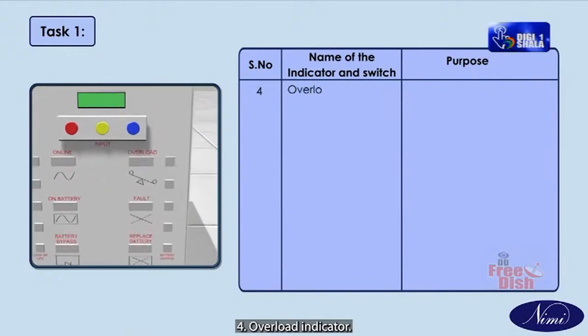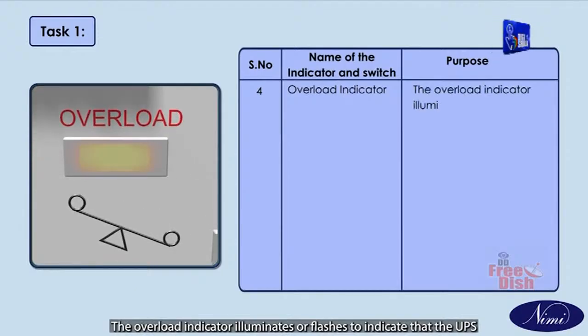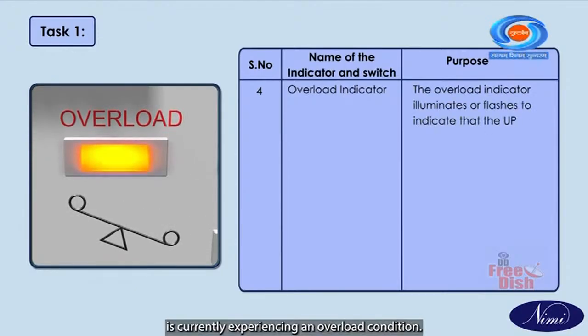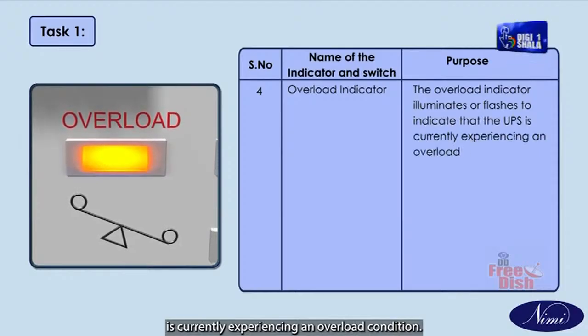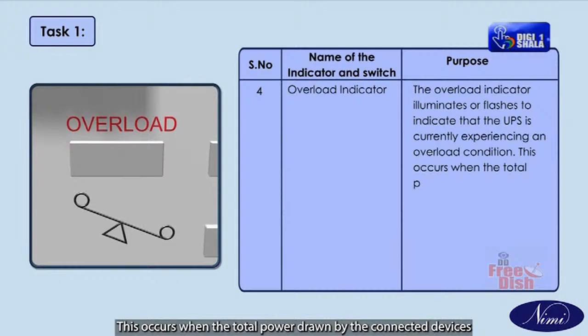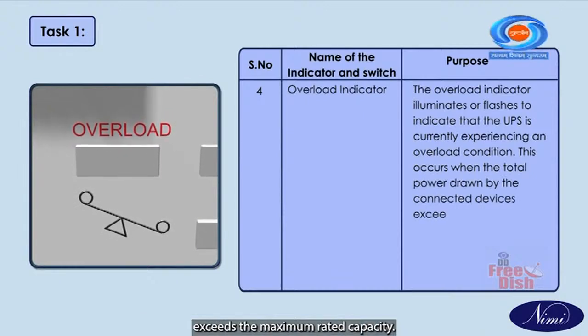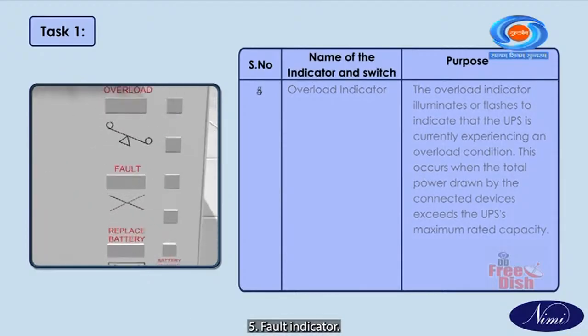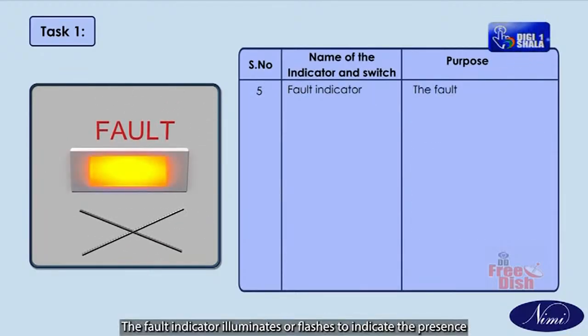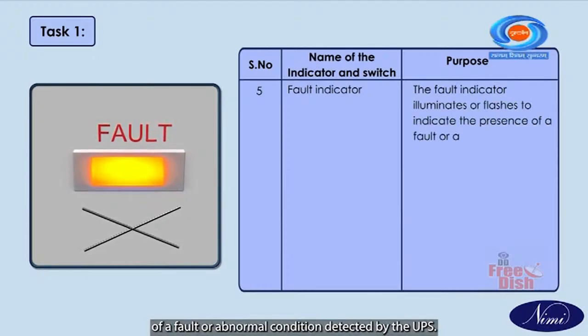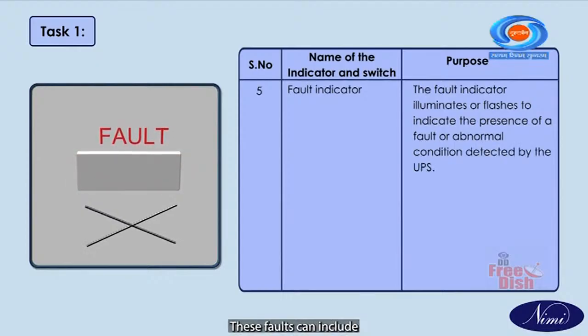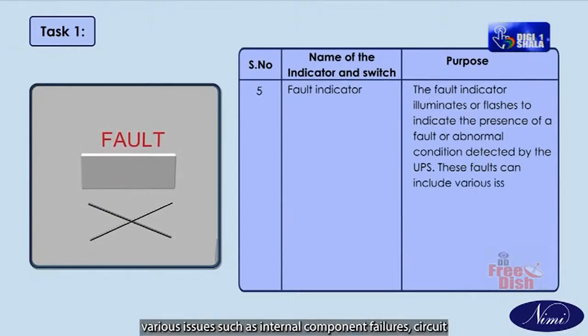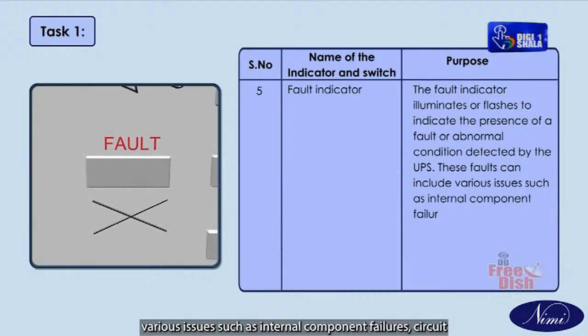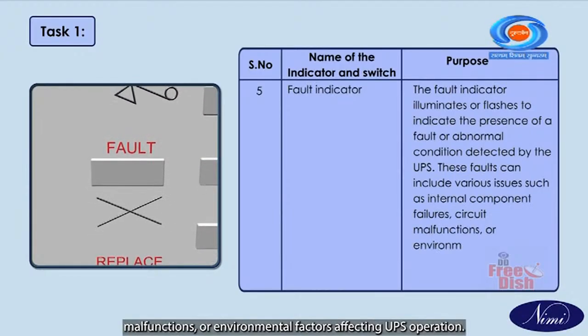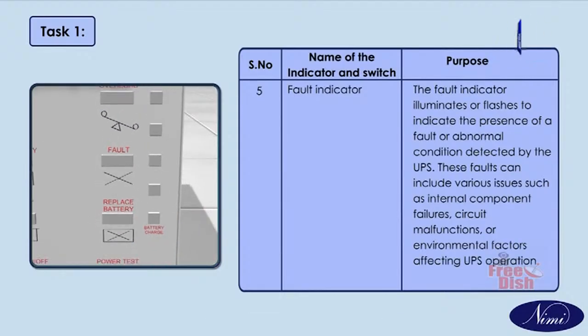Number 4. Overload indicator. The overload indicator illuminates or flashes to indicate that the UPS is currently experiencing an overload condition. This occurs when the total power drawn by the connected devices exceeds the UPS maximum rated capacity. Number 5. Fault indicator. The fault indicator illuminates or flashes to indicate the presence of a fault or abnormal condition detected by the UPS. These faults can include various issues such as internal component failures, circuit malfunctions, or environmental factors affecting UPS operation.